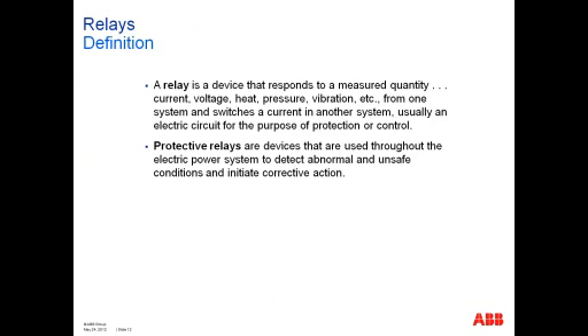So with that, a definition: a relay is a device that responds to a measured quantity, voltage, current, heat, pressure, vibration, from one system and switches current into another system, usually an electric circuit, for the purpose of protection and control. That was a definition from the 20s, and today perhaps a more modern definition would be protective relays are devices that are used throughout the electric power system to detect abnormal and unsafe conditions and initiate corrective action.